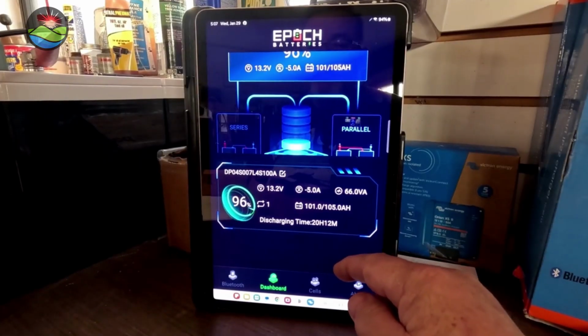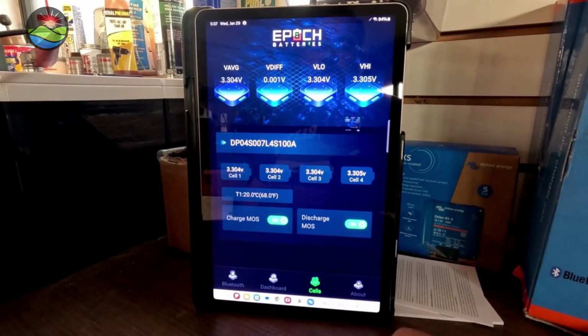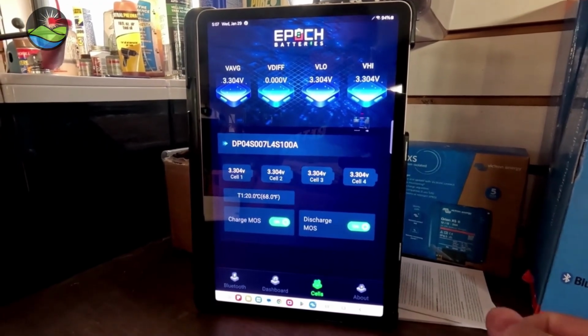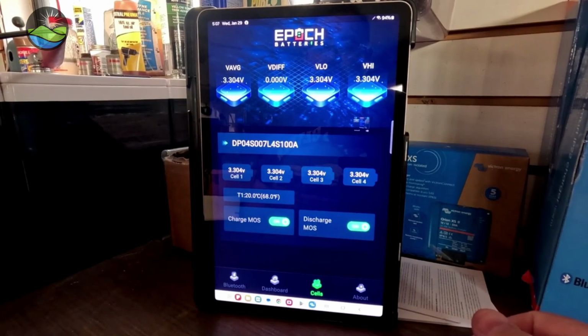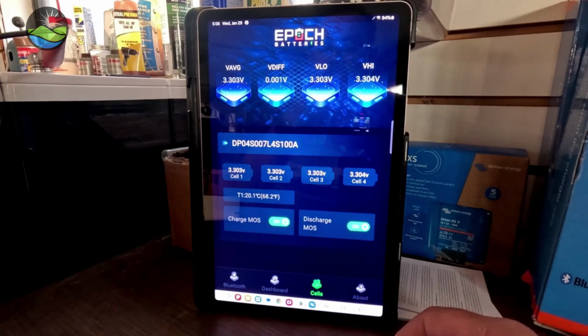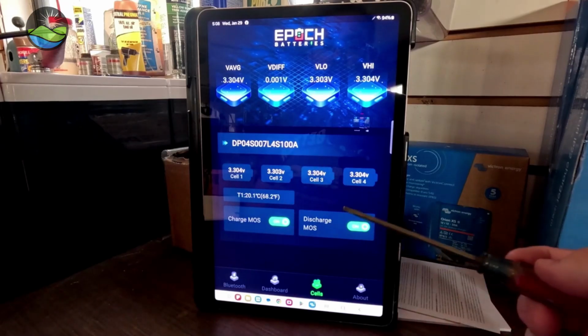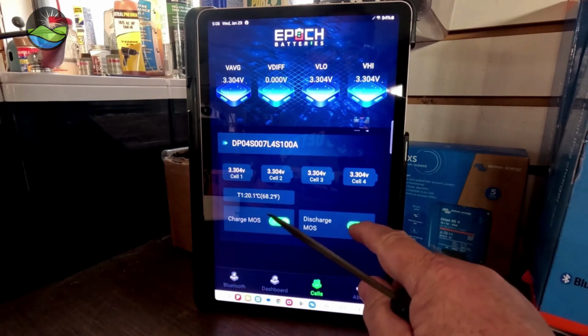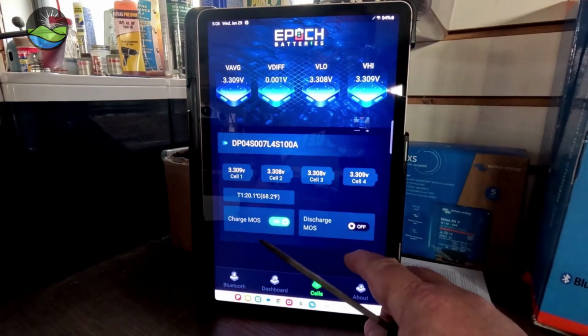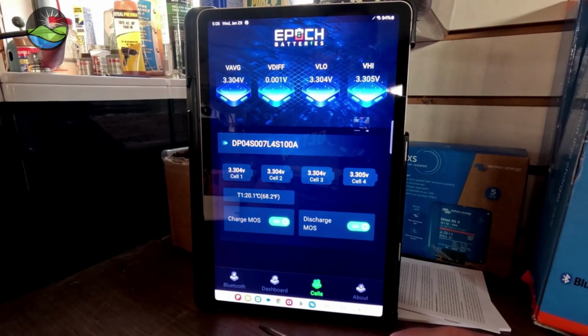Mainly you want the BMS to control these MOSFETs, for several reasons. Number one, the BMS is monitoring all kinds of parameters: temperatures, voltages, and currents mainly. If there's an exceedance in any of those for a safe operating envelope, like low voltage cutoff, high voltage cutoff, low temperature, high temperature, or short circuit, the only way the BMS has control is to stop the charge or stop the discharge. So if cell voltages get too low and the BMS detects that, it's going to shut off the discharge MOSFET itself. You don't have to do it. So let the BMS do the controlling of these MOSFETs, generally speaking.